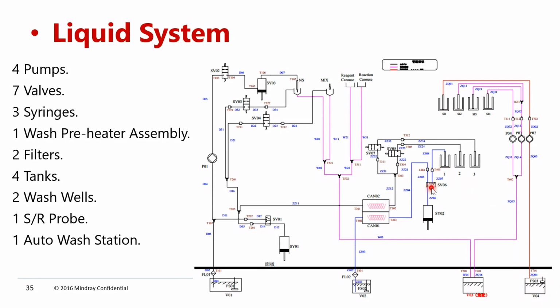And again, every cycle will happen 2 times, no? So again this probe will go down and dispense the detergent. Again this probe will aspirate the detergent. So 2 cycles completed for one cuvette. Then the cuvette disc will rotate, and this cuvette will move here. Here it will dispense the water, aspirate, again water, aspirate. So this is a diluted waste. This purple line indicates diluted waste, low concentrated waste. The red line indicates high concentrated waste, the blue line indicates detergent, and the black line is a water dispensing line.